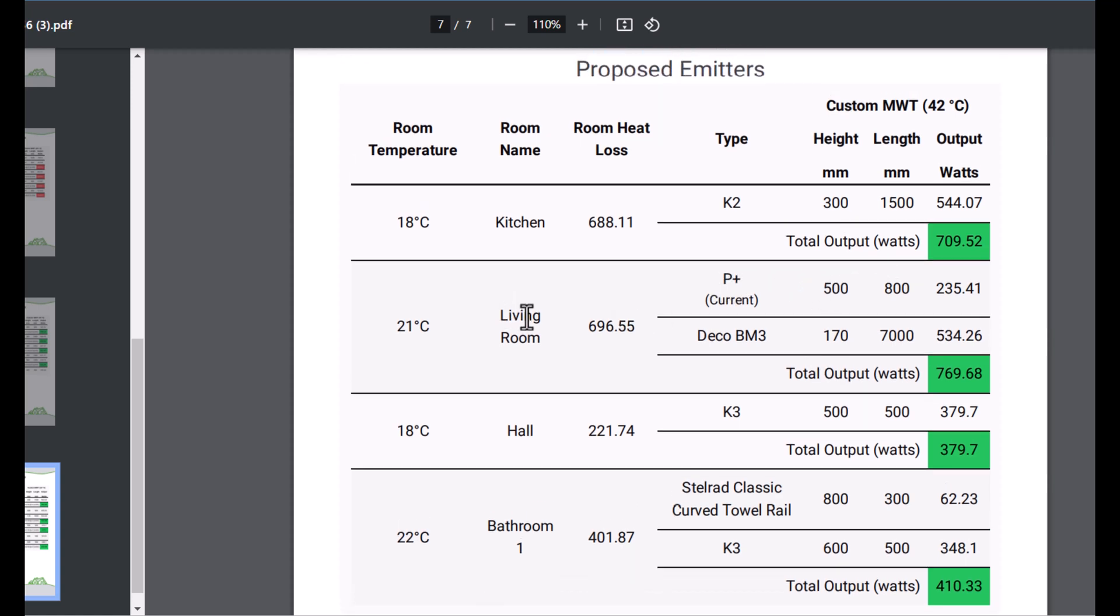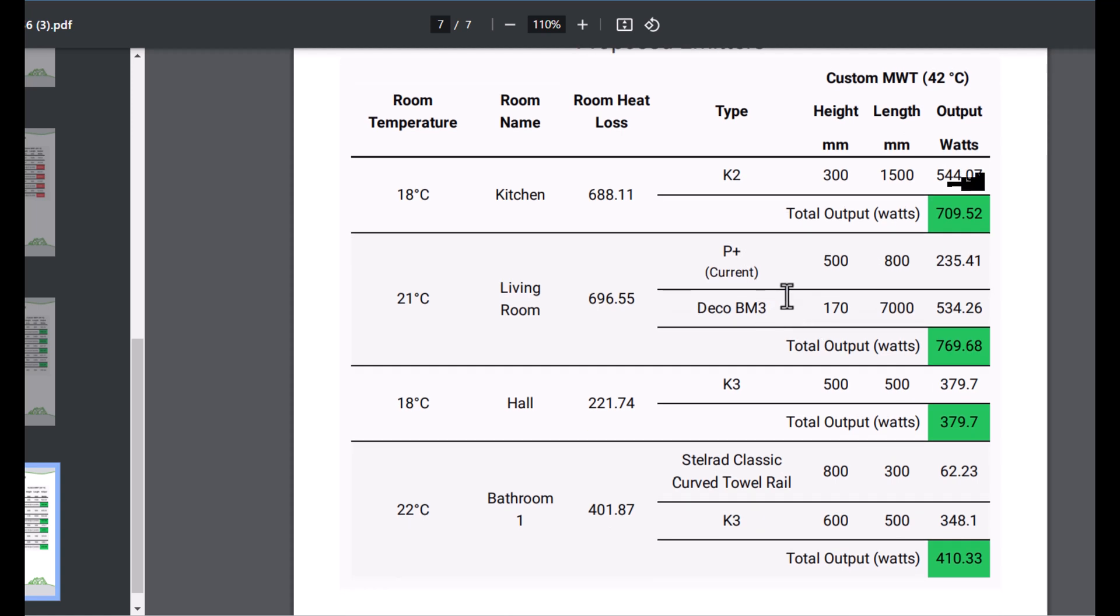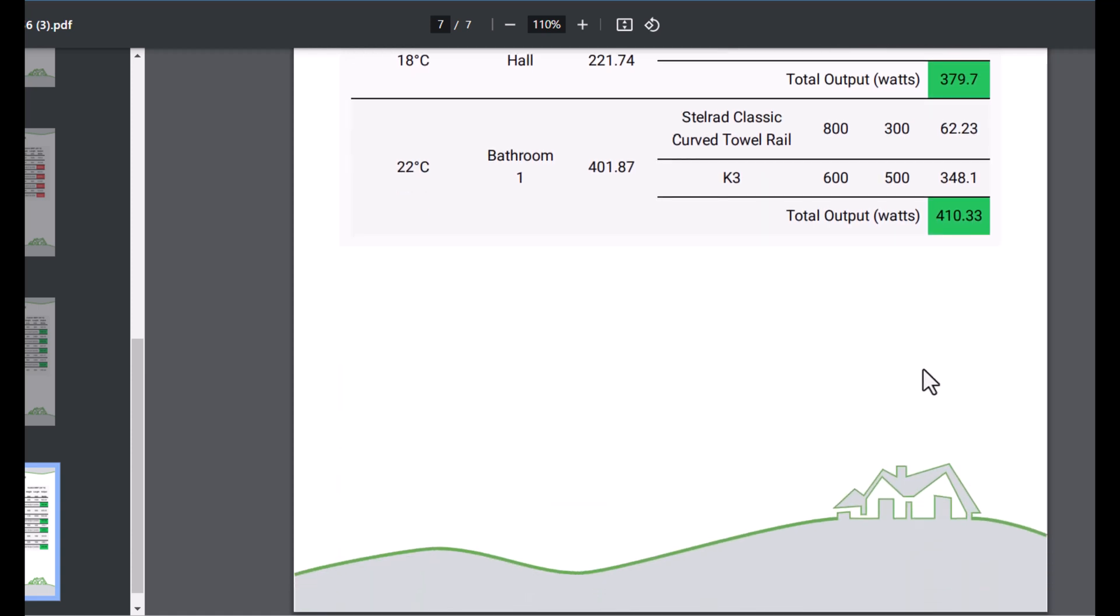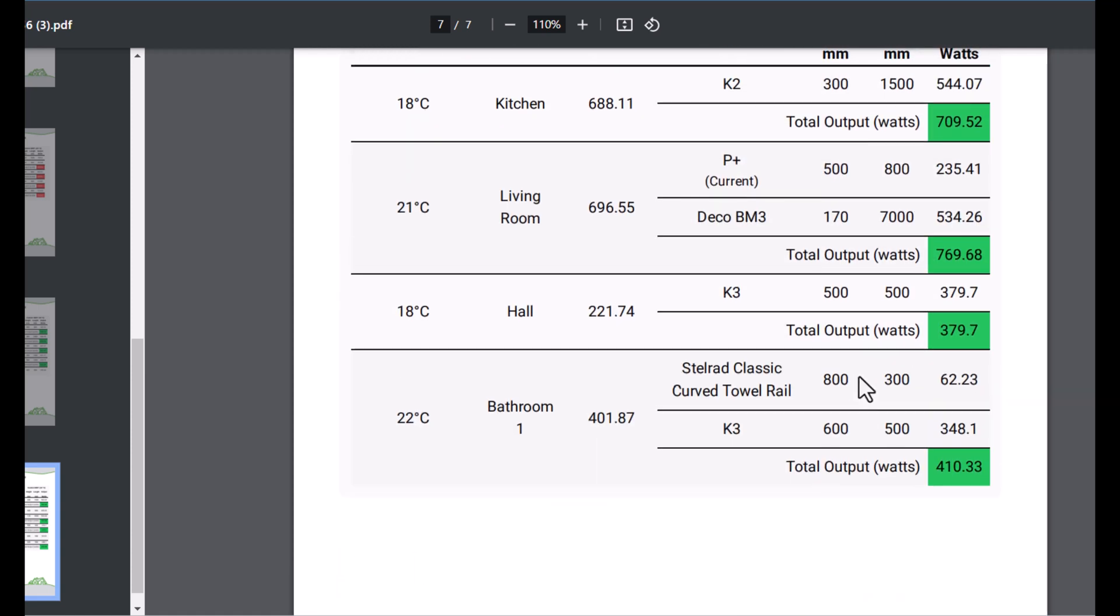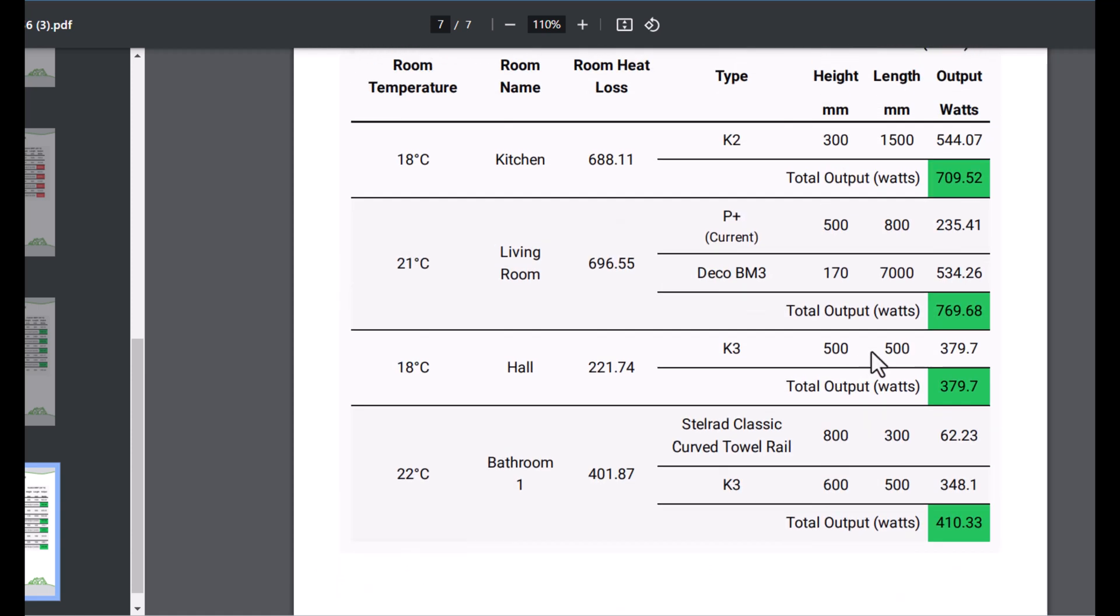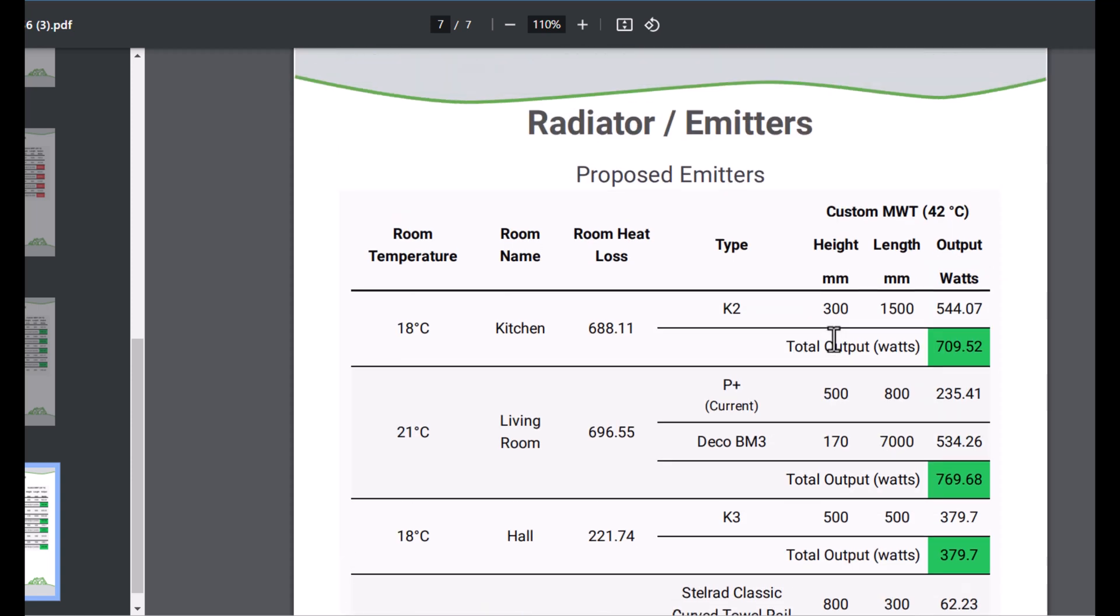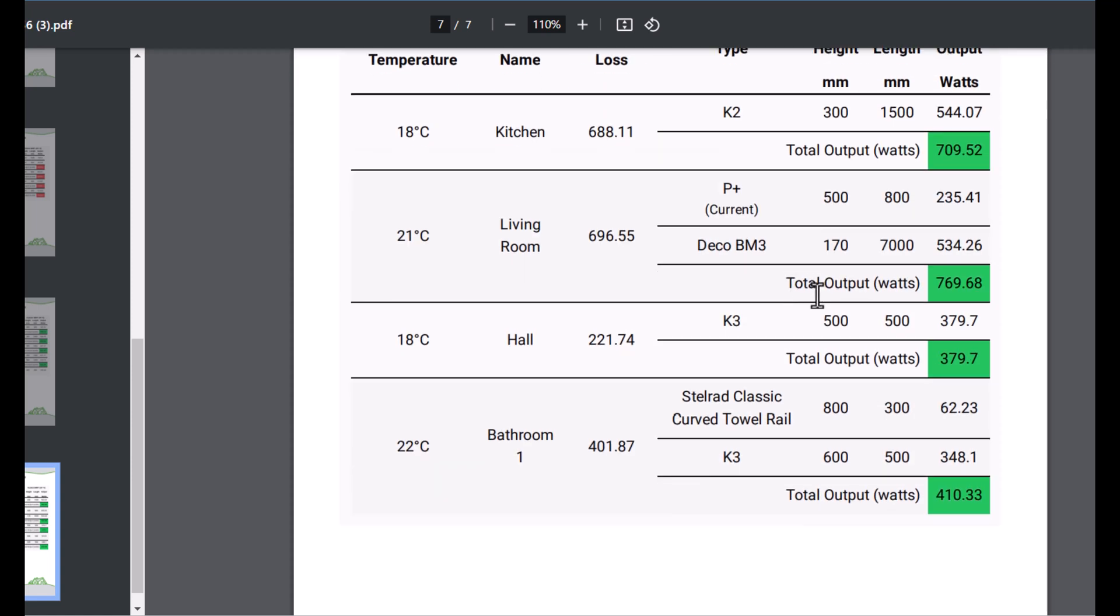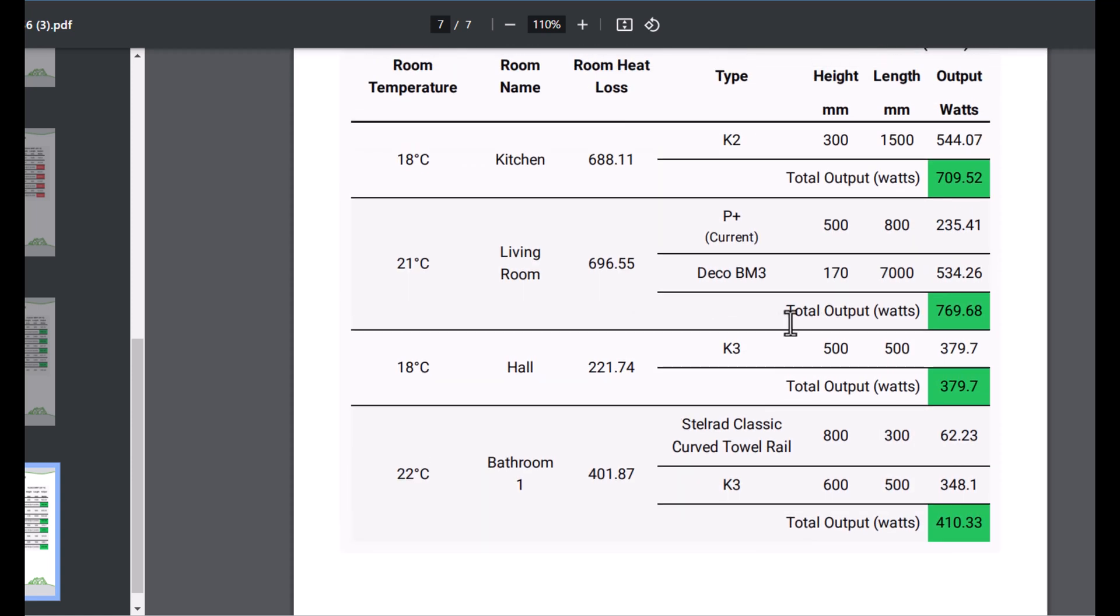I scroll down again. What we're doing is we're highlighting any radiators, so in the living room here, any radiators that aren't going to be moved, we put it in brackets of current. Then here we've got some thermoskirt product as well to complement the existing radiator. So this client is going to be happy because now our new proposed radiators, our emitters I should say, are actually going to meet the demand there.